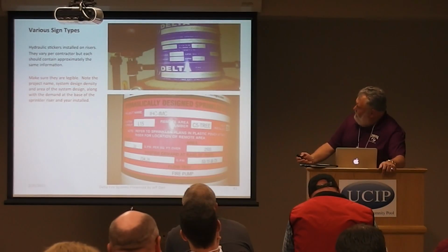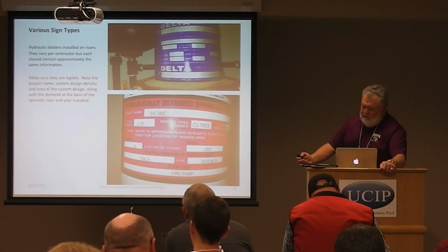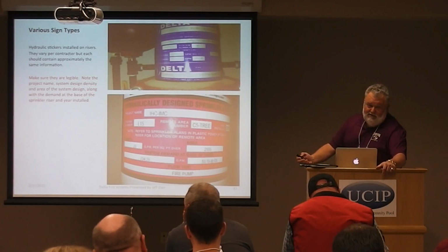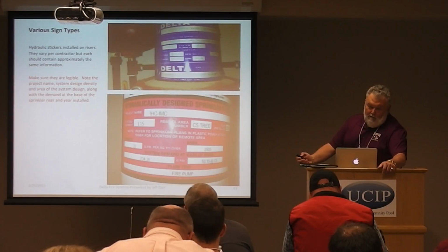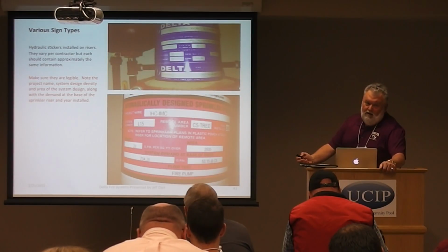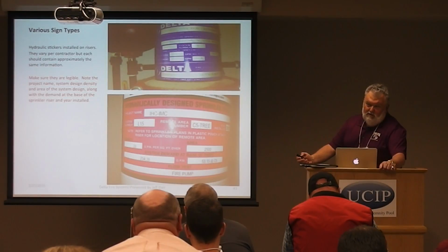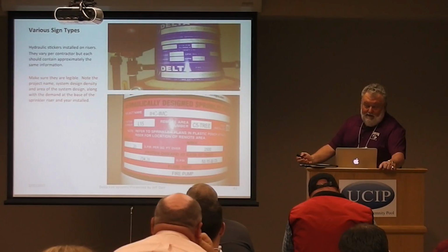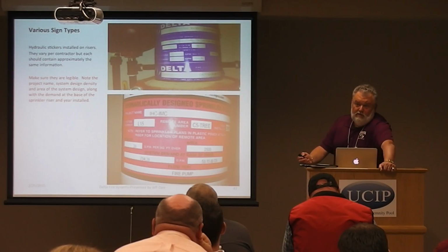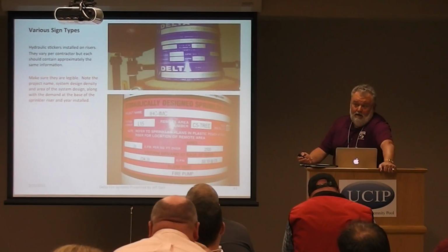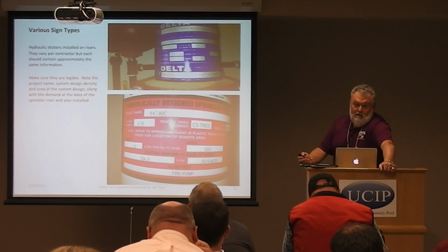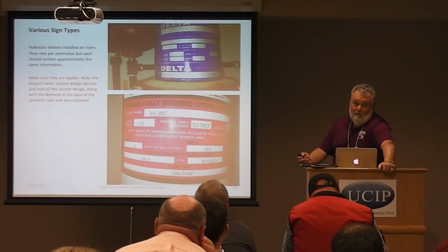Here, they come from various companies, have different layouts and different types on them. There's just 2 of them. But they basically have the same information: the year the system was installed, what it was designed for, pressure requirements. So we're getting calls quite often: hey, come and look at our riser, we see no hydraulic sign, can you help us with that? About the only way we can help if you don't have the original design drawings is we'll have to go back in and do a risk analysis assessment, actually calculate it for you. And insurance companies are getting more apt to do that. I understand you guys are all county staff, but from the general public, we're finding that's more and more of a problem.